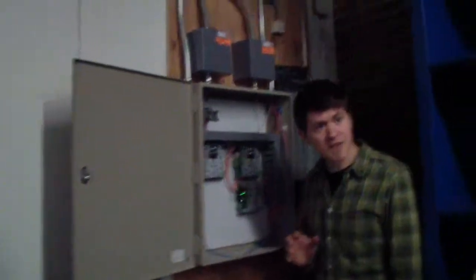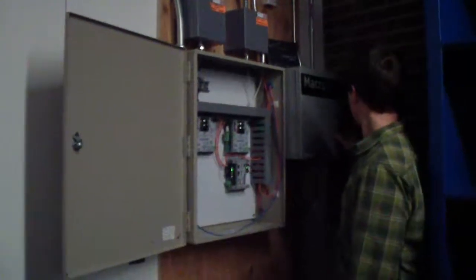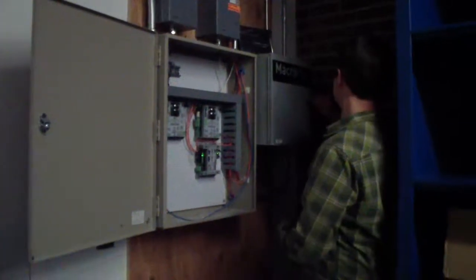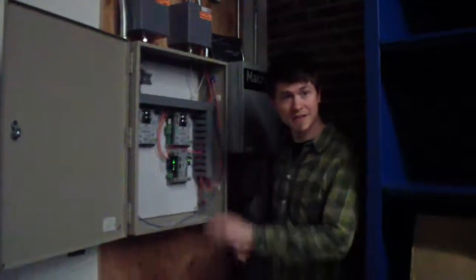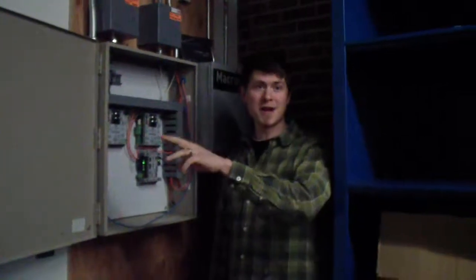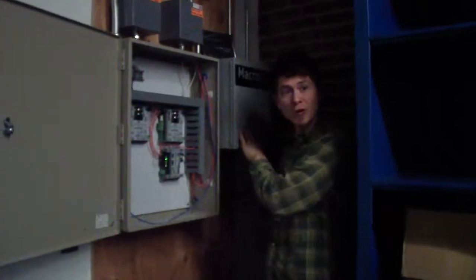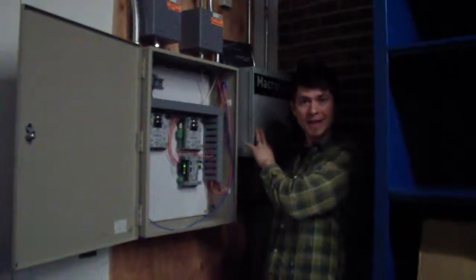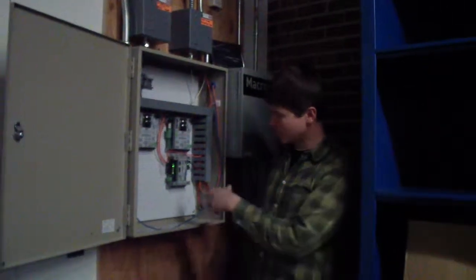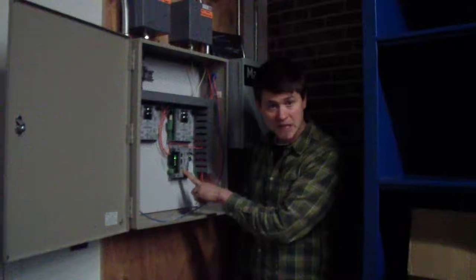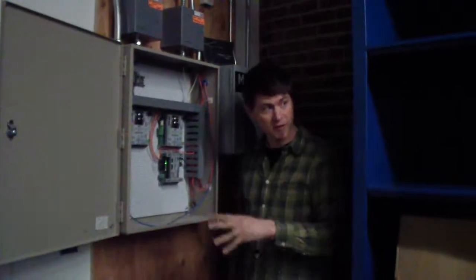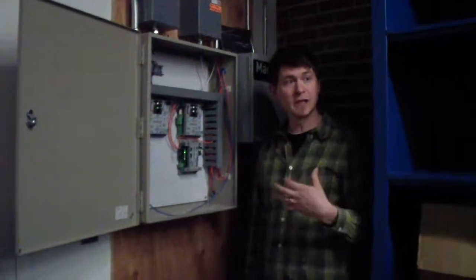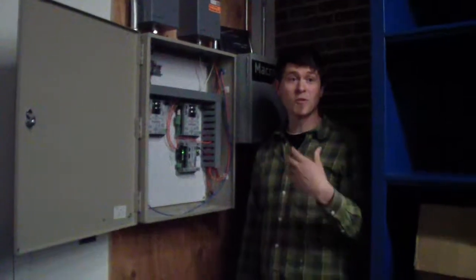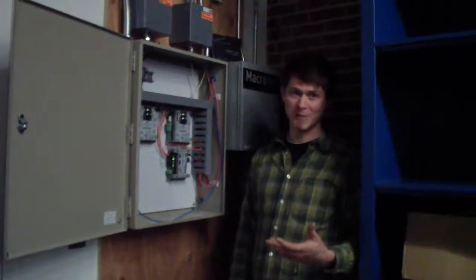So here we have the cards for the destrat fan controls, and this is the macro air controller. So this takes the Yaskawa drive Modbus. There's a ProtoNode controller in here. It's a FieldServer device that translates into BACnet, which is what we see through our AMR. And this is how we communicate back and forth. And we're actually able to read what the frequency is of those fans, as well as write to them what frequency we want it to be at.